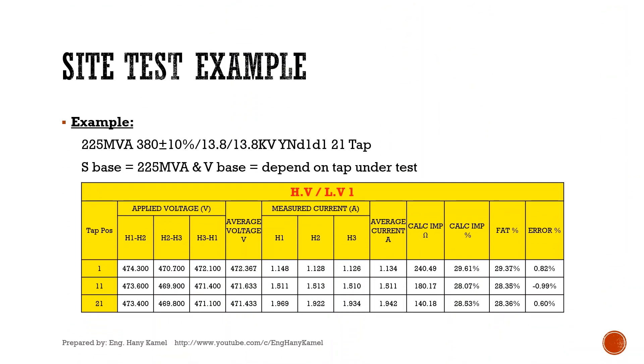This test will be performed for the maximum voltage tap, normal tap, and minimum voltage tap. All recorded values will be used to calculate the impedance at site for each related tap. Comparison will be done between site and factory values, and the error will be calculated. Care should be taken for the base power and voltage to make the right comparison.